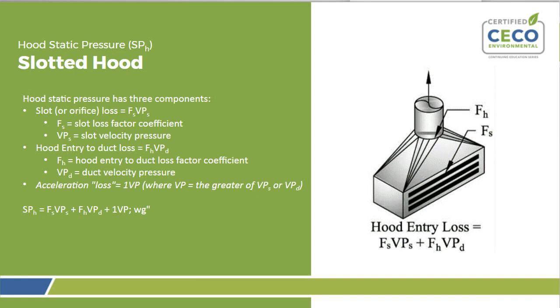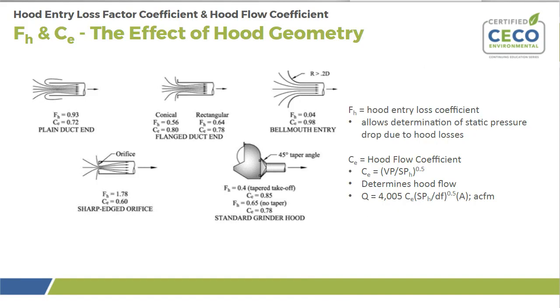And again, geometry plays a great factor in the loss coefficient. The geometry with wider tapers and wider entry angles will be more efficient. The plain duct end type hood, on the left, has a loss coefficient of 0.93, and simply putting a flange at the end of the duct reduces the loss coefficient to 0.56. So we have less loss simply by having that flange on the end.